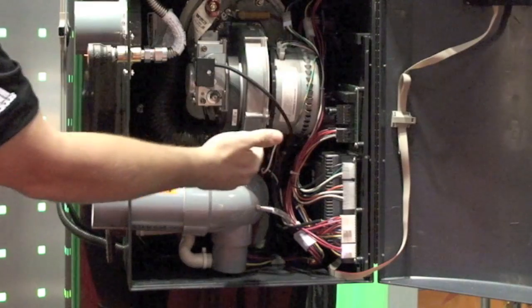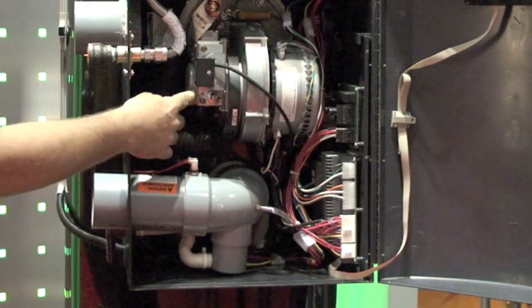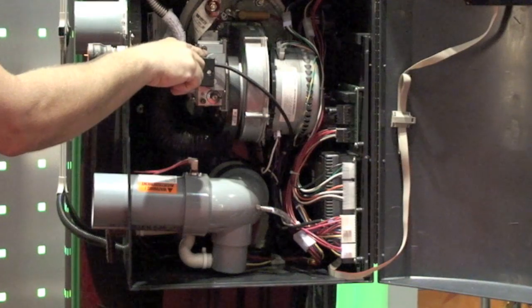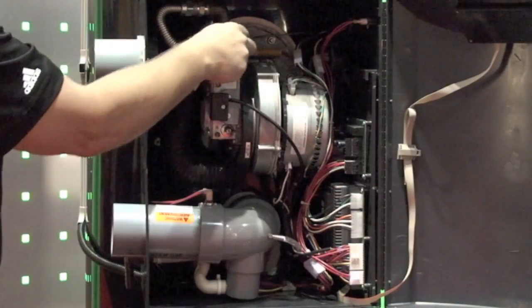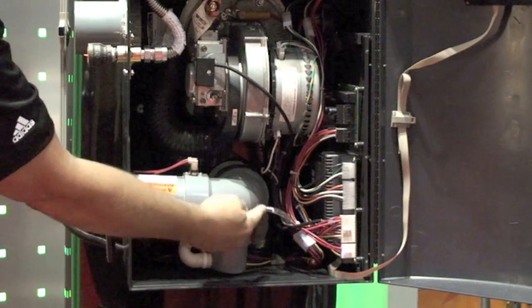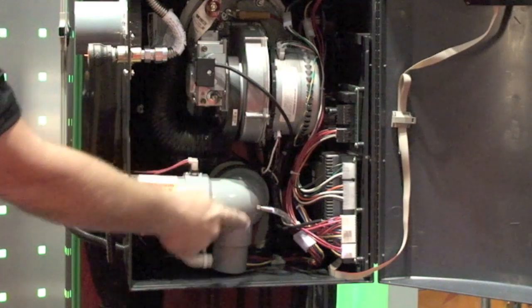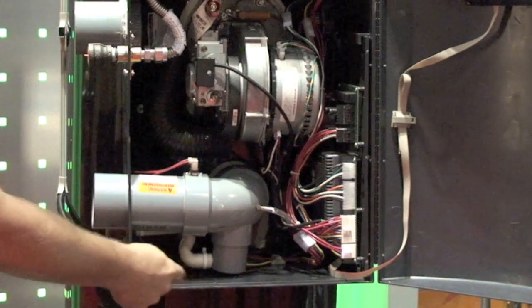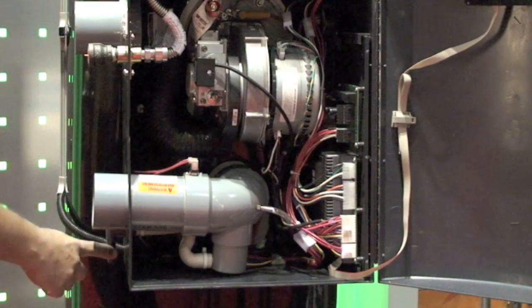The fan is easy to get at. This is our gas valve with the gas valve adjustment right here. You can monitor incoming pressure simply by taking a screwdriver on this needle valve and putting your manometer over it. We have shutoffs which isolate the gas valve. On the combustion system here is our exhaust — we're monitoring pressure in the vent system to make sure there's no back pressure or blockage. We monitor our high limit through this high limit system, and the exhaust has a trap built in which allows condensate to flow out of this connection.